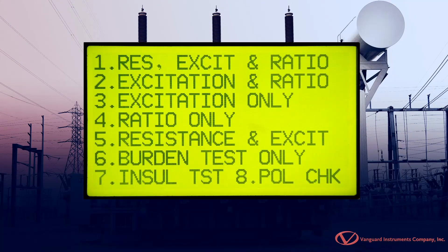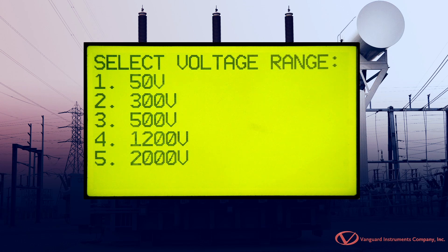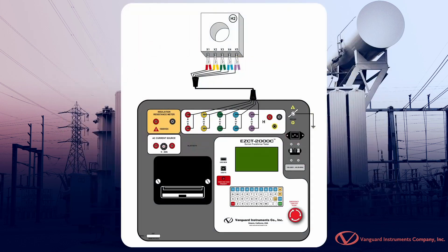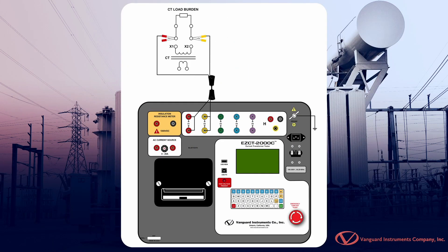The EZCT-2000C can perform excitation, current ratio, polarity, and phase angle tests. It also automatically demagnetizes the CT when performing excitation tests. The EZCT-2000C can also measure the insulation resistance of the CT's secondary winding as well as measure the CT's load burden.